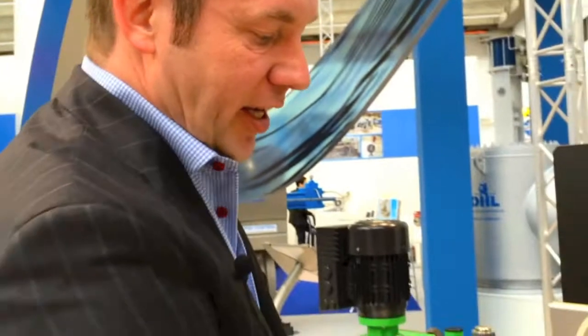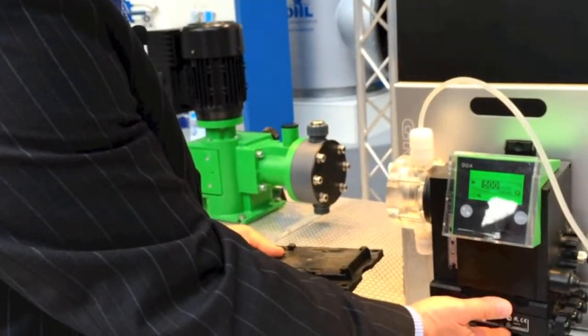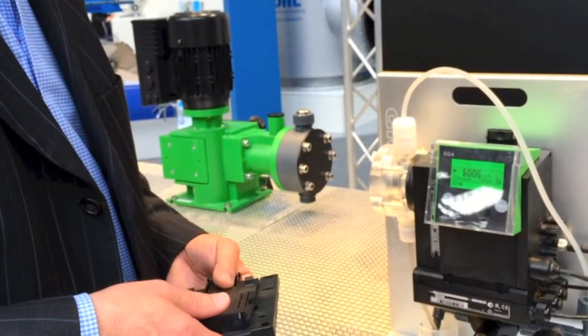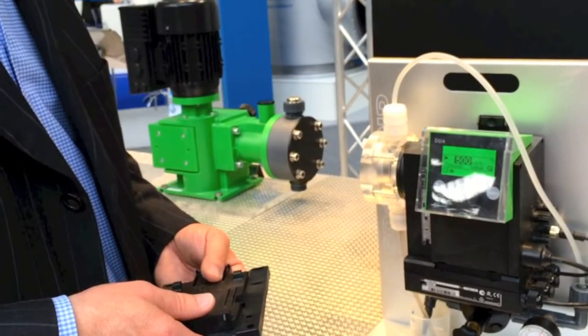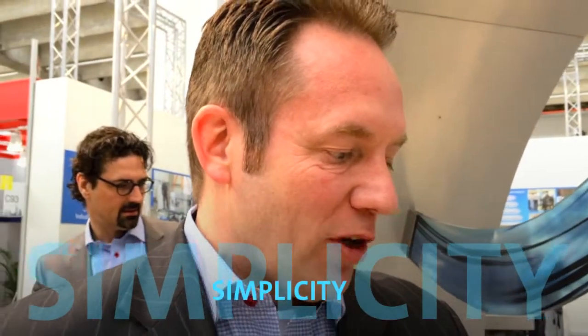The other benefit is if you want to install the pump into a SCADA interface, then we have these control boxes, and they can be clicked below the pump, also afterwards. So if you decide to integrate the pump into a SCADA system six months after you install the pump, no problem. You remove the base plate, take the control box, click it below the pump, and then the pump is integrated into a SCADA interface. So that is one point, the modularity.